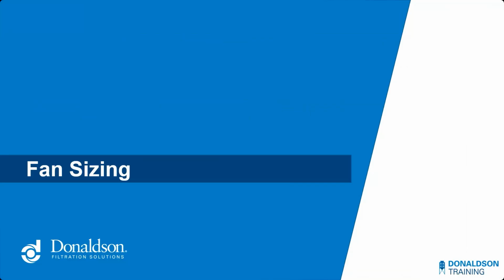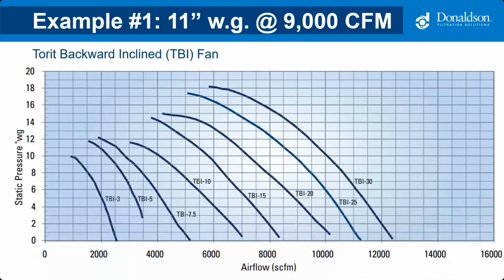Let's talk about fan sizing. Let's do a quick example. We'll start with a small system for the first example. Let's say we're designing a system for 9,000 CFM at 11 inches water gauge. This might be a welding operation with a cartridge collector or something similar.